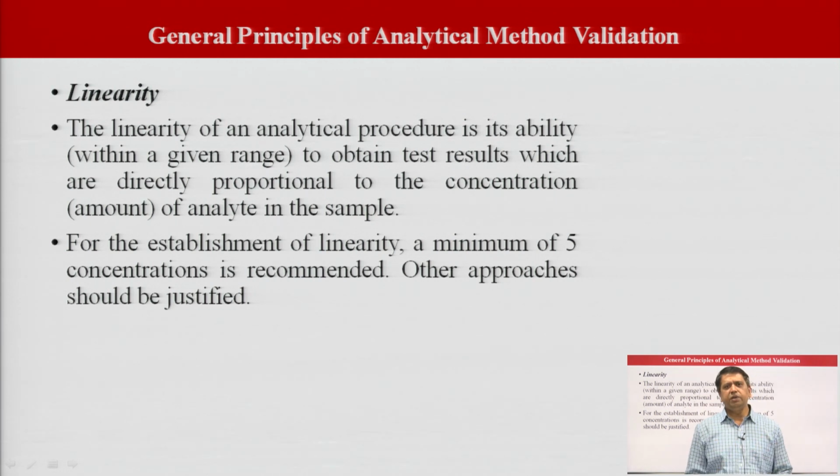So, linearity basically establishes that the response received in the detector of any instrument is directly proportional to the concentration of the analyte. And for the establishment of linearity, a minimum of 5 concentrations is recommended and other approaches should be justified.